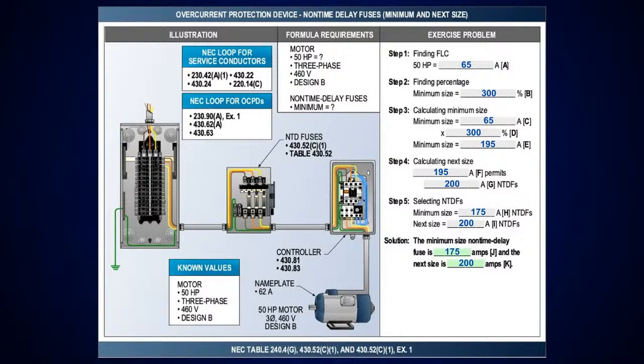I mean, even when NFPA published our books, the table still stated the same in 430.52, and it says maximum, but that's the maximum percentage for that table. And you got people like Jeremy and Ted and all of them, they come in, that ain't right, there's no maximum, there's no minimum. And I'm like, I don't know what y'all arguing about. You going to tell me that the staff at NFPA is all incorrect too? Because they added it. We had 3 editors at NFPA looking at the technical validity of what we published, and we've had it in the books that way 30 years. I mean, now all of a sudden it's wrong because they say so. And when have you ever heard about having 2 maximums?